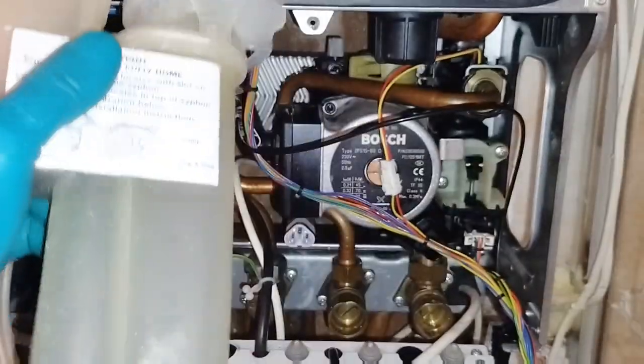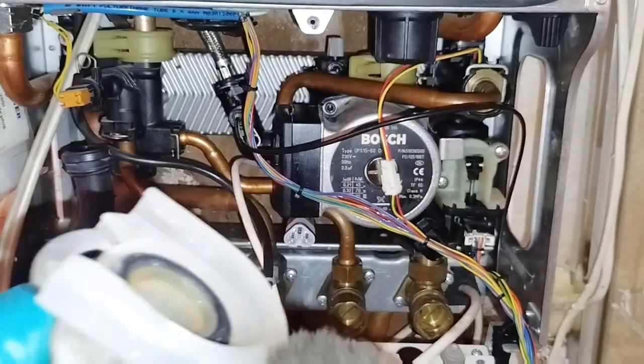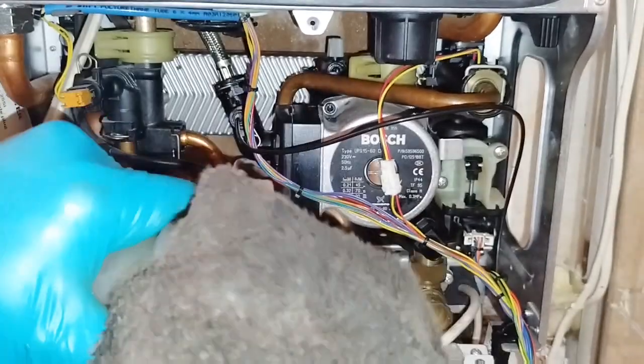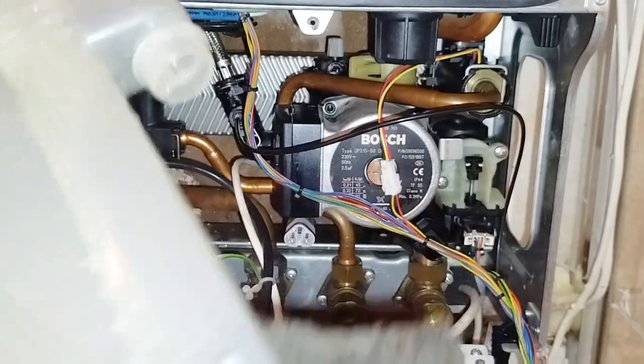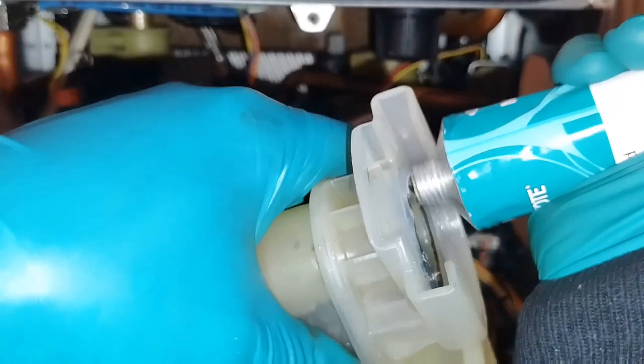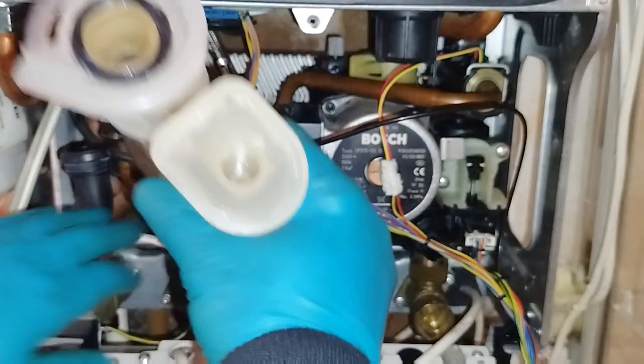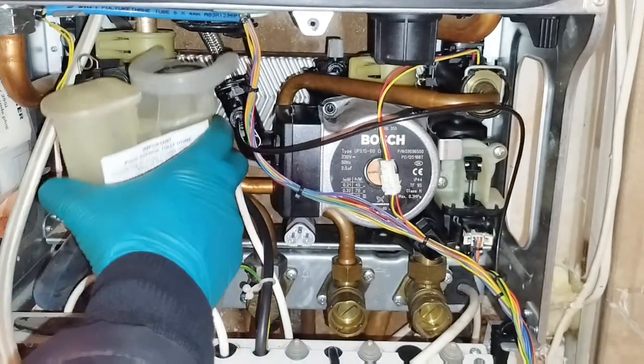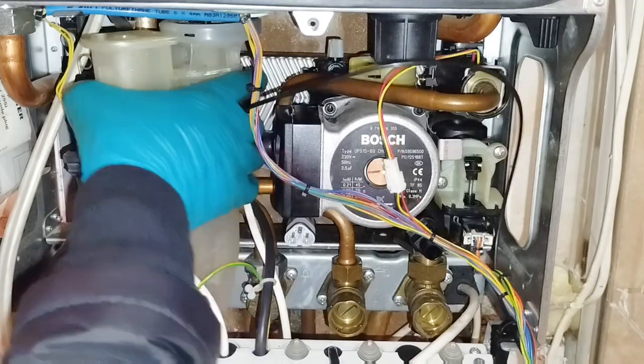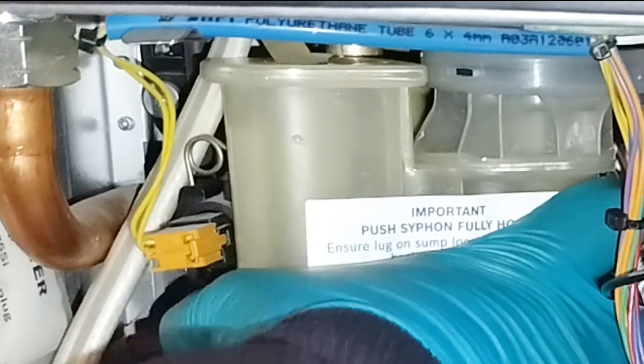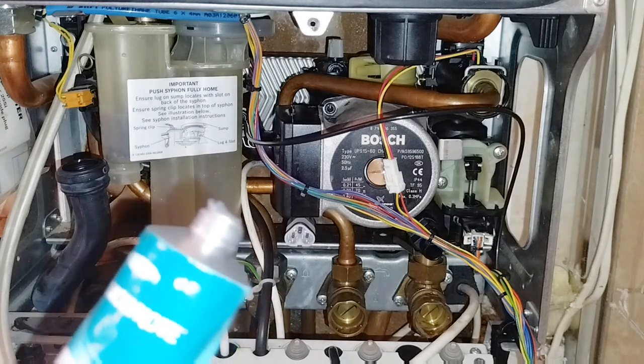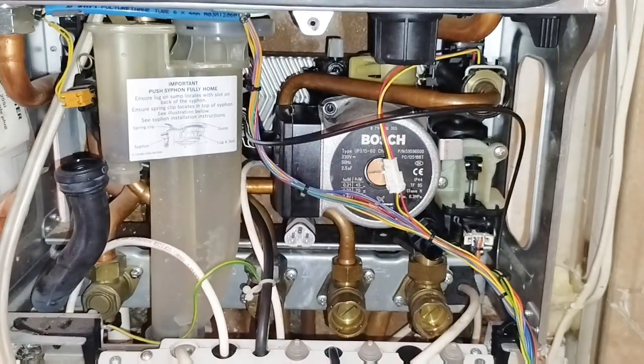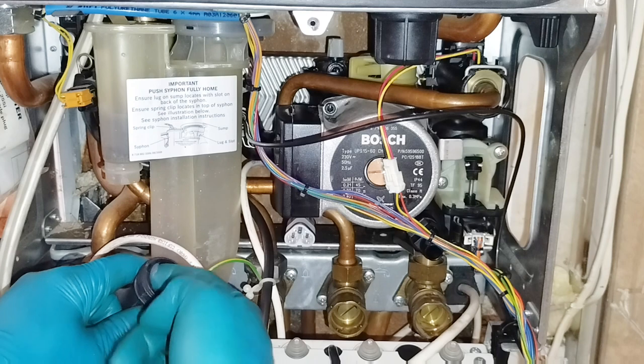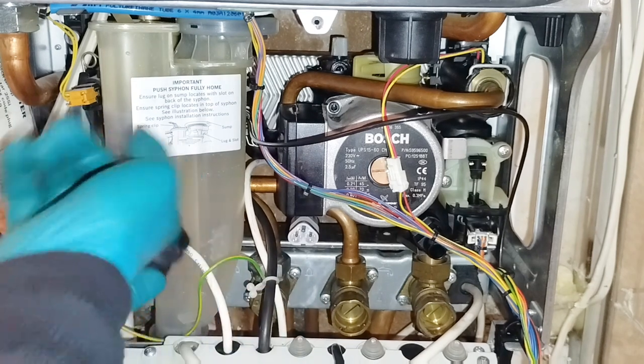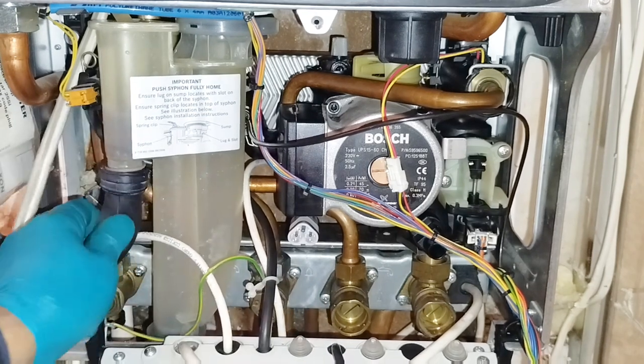So the trap goes back into position. Always dry it off so it doesn't give you any confusion if it's still dripping or if it's got residual water in it. If you push it in, you can't tell, and even if it's leaking, you'll think that it's just residual water. So dry it off, put some silicone grease on top of the big old O-ring it's got, put the trap into position, and the little locking mechanism will hold it in its position at the top. Even more silicone grease, this time on the rubber hose which will connect onto the condensate trap, and this way you don't have to push and shove and struggle with the hose, and it goes on very nice and easy.